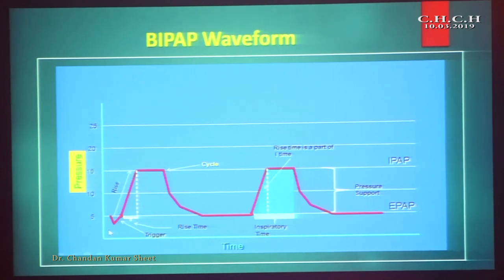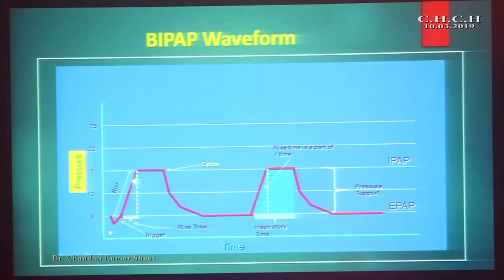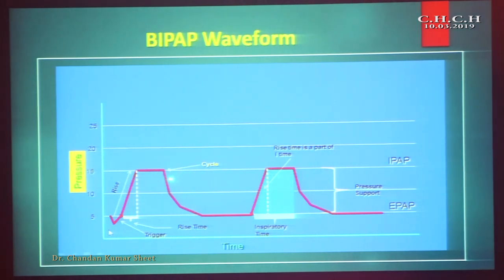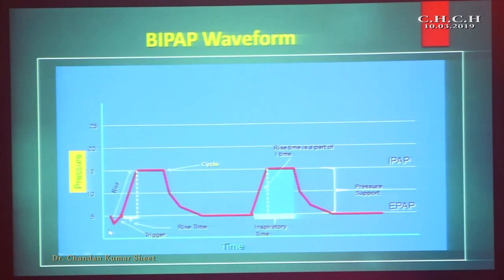This is the pressure-time graph, where some negative pressure is generated by the patient and the ventilator senses it, then delivers the preset pressure — this is IPAP. The total time when IPAP is applied is the inspiratory time. The transition from IPAP to EPAP is the cycle, followed by the expiratory time. The trigger to peak IPAP is called rise time, and the difference between IPAP and EPAP is pressure support.